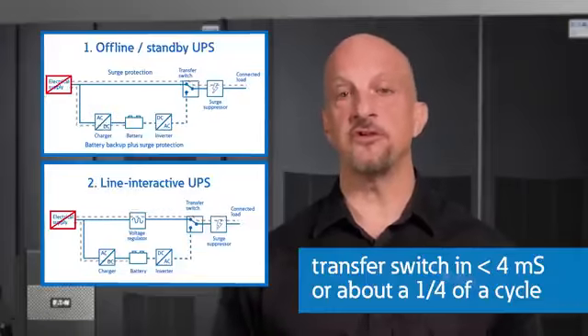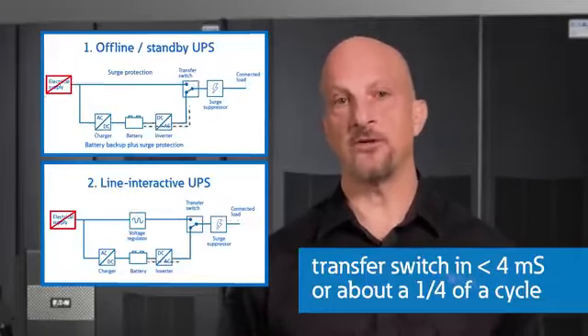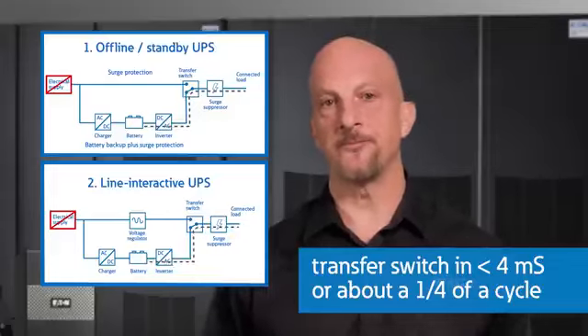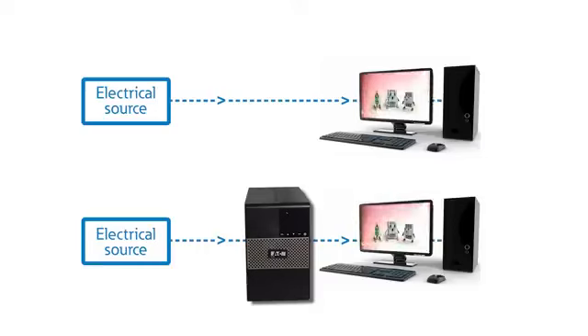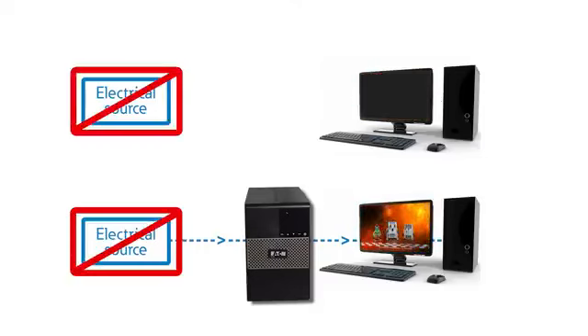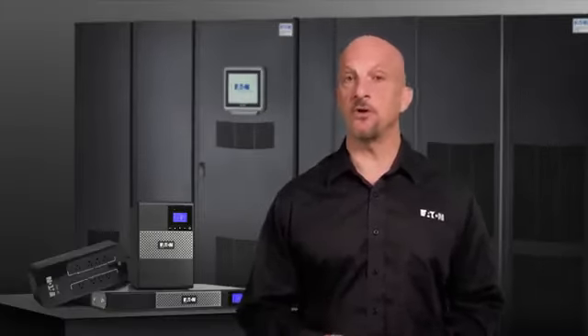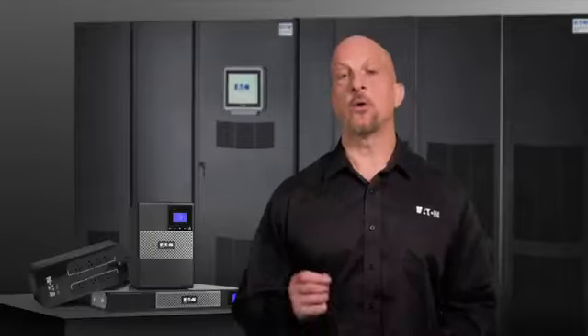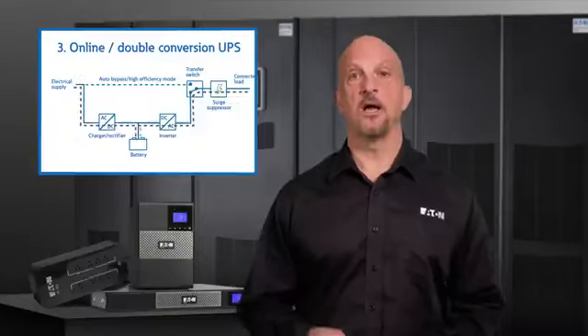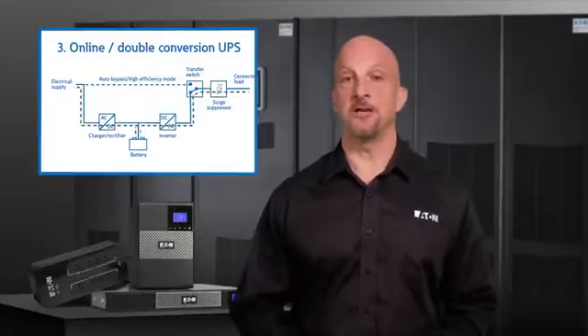The standby and line interactive UPSs will transition to battery well within 4 milliseconds, or about 1/4 of a cycle. This transition is quick enough that the computer doesn't even realize there's a loss of power. This also allows them to be more efficient, but the trade-off is less power conditioning for the loads. For some special loads in manufacturing processes or other applications that don't follow the ITIC curve, or where power quality is very poor, a double conversion UPS may be needed.